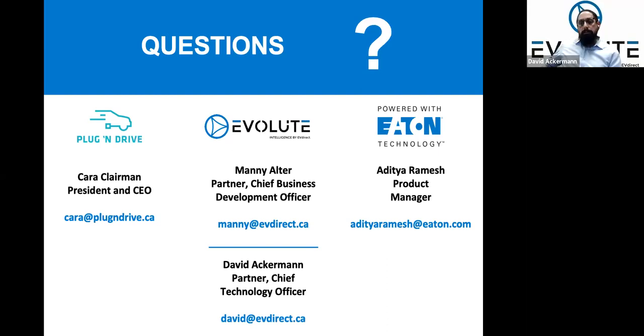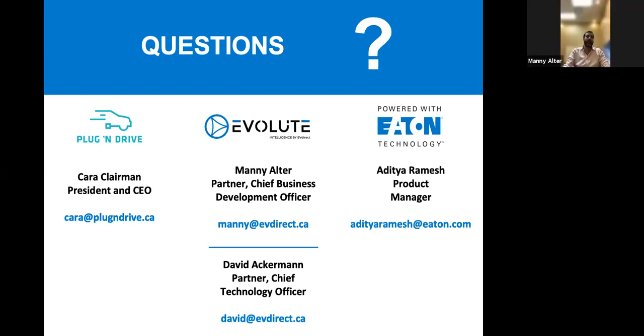The value add of the Evolute to a developer is that they're not investing in charging stations, especially when a building spec'd today won't be occupied for 2 to 3 years. It's very hard to pick hardware today when that hardware can be obsolete in 2 to 3 years. So the Evolute allows the developer to put in provisions for 50, 60, or 100% EV capability.